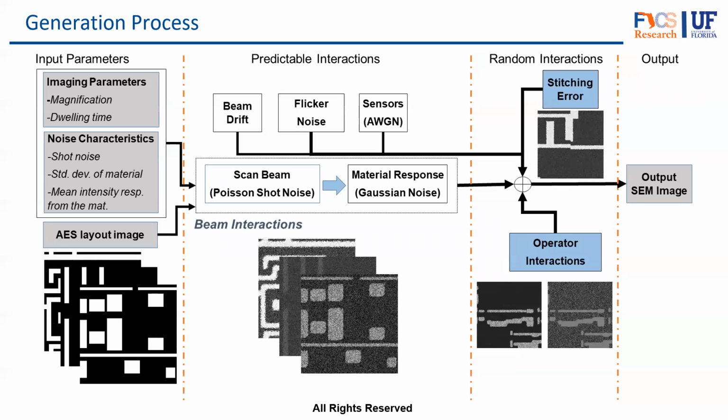The SEM produces a single channel grayscale image with the intensity of each pixel representing the properties of the material. The SEM directs the scanning beam towards the sample under study, and the sample in response releases electrons towards the detector. The pixel intensity value is a scaled response to the number of electrons received in response to the scanning beam. This is a simulatable process.